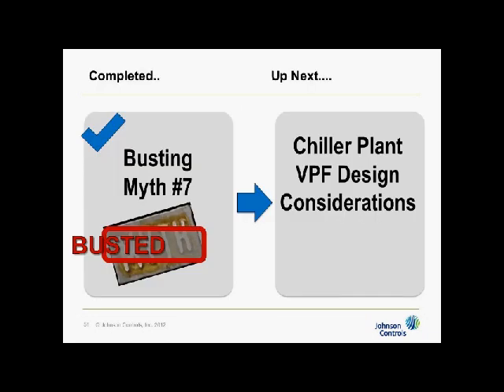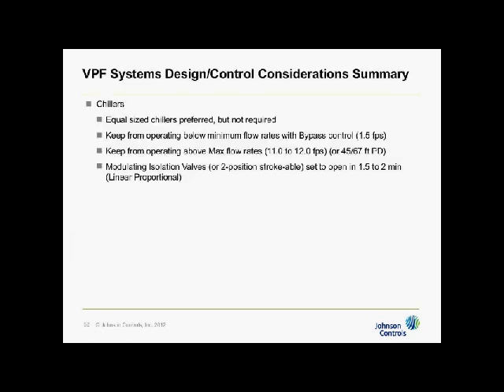So we finished busting myths number 6 and 7, which were about flow and speed, and now we want to look at some design considerations for VPF. We'll look at them for the chillers and the pumps and the towers, but starting with the chillers. First of all, equal-sized chillers are preferred but not required. There's a misnomer out there that you have to have equal-sized chillers. It's better if you do. It's easier if you do.